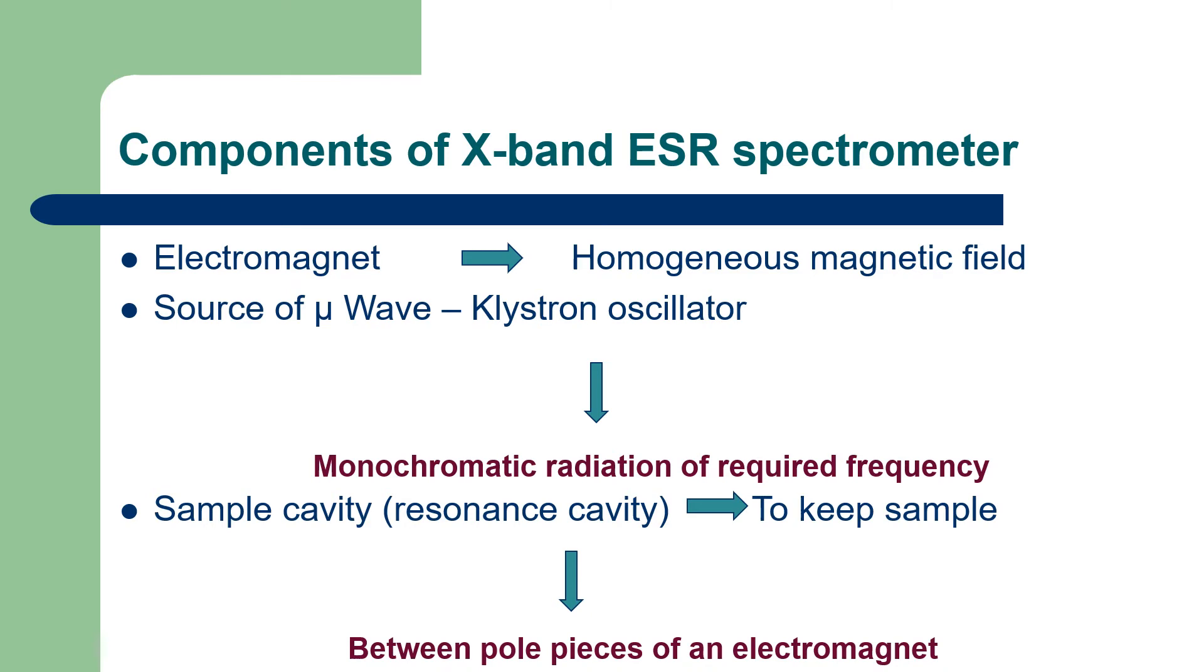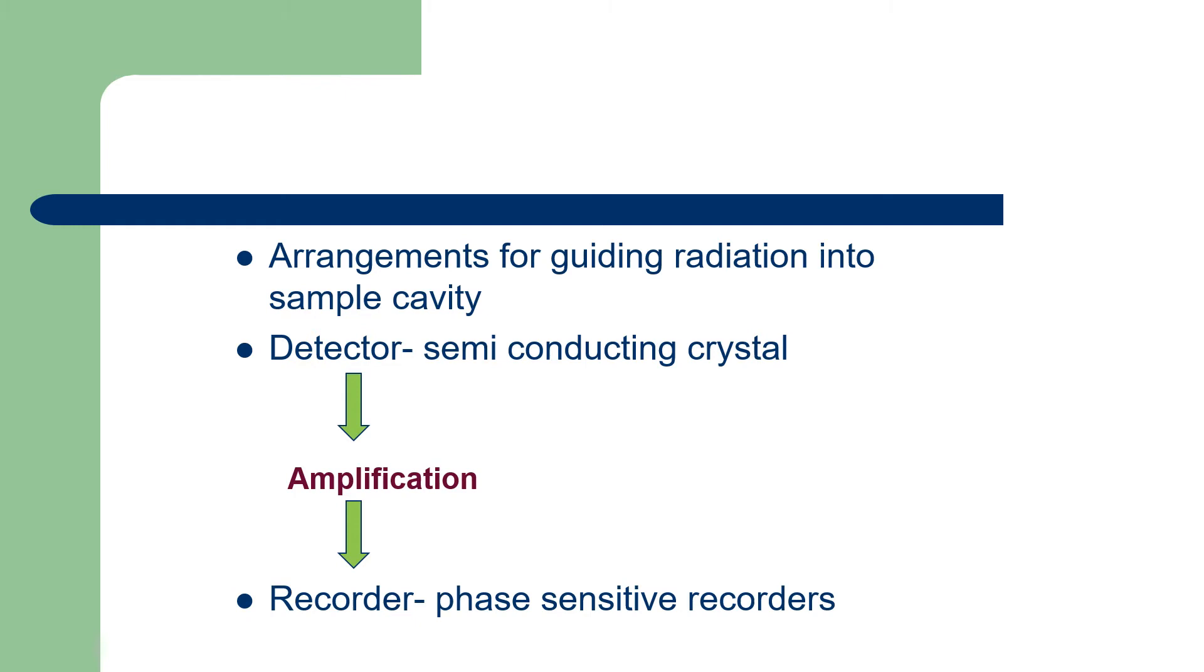The third component is a sample cavity or resonant cavity. The sample cavity is used to keep our sample and is placed between pole pieces of the electromagnet. The fourth component is the arrangements for guiding the radiation emitted by the source into sample cavity. Then fifth one is a detector. We can use semi-conducting crystals as a detector. After detection, we amplify the weak signals using an amplifier. Then this amplified signal is sent to the recorder.